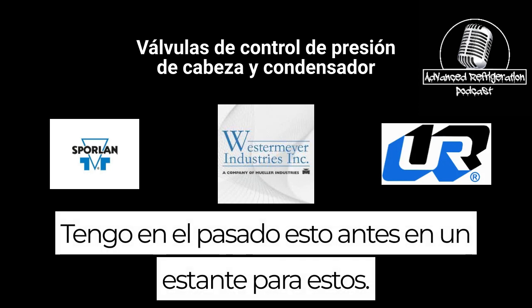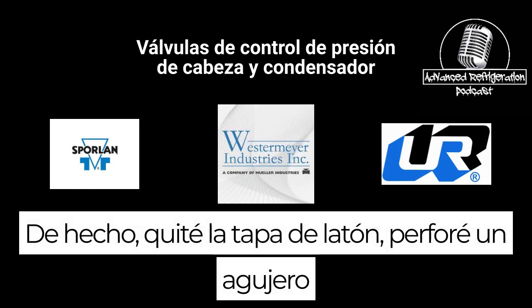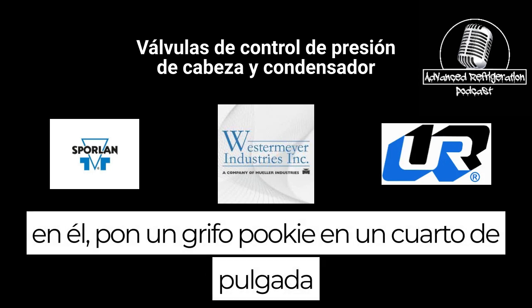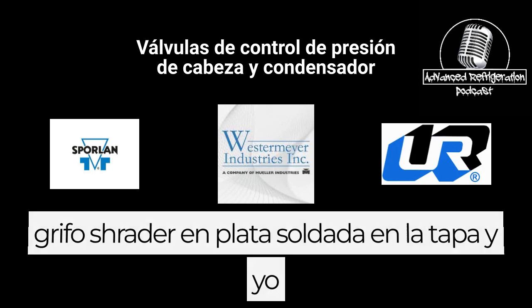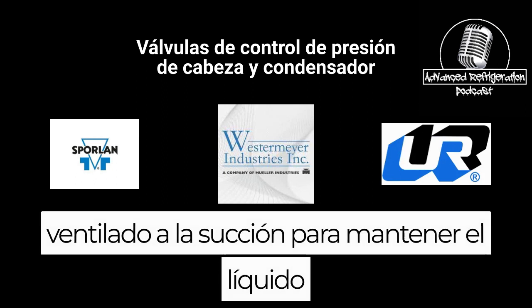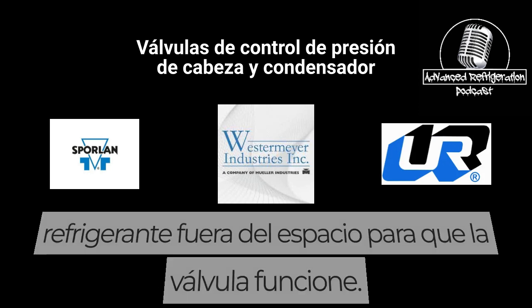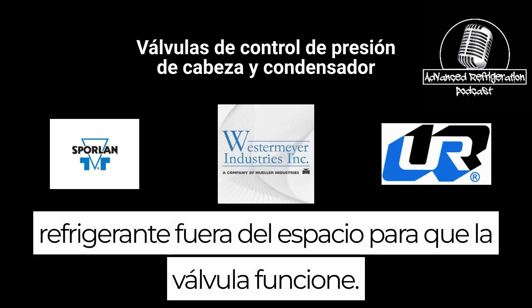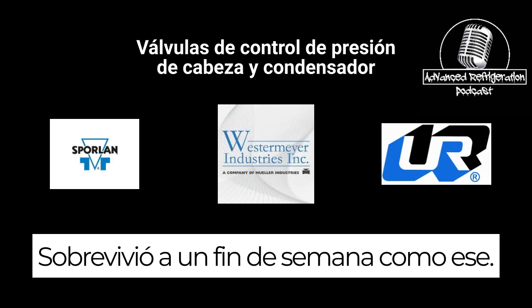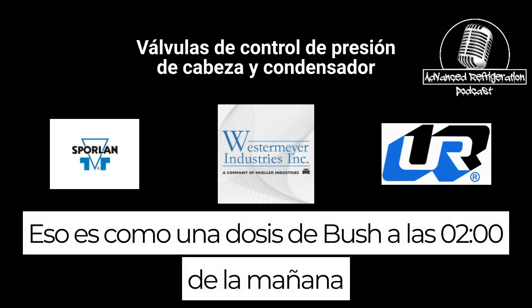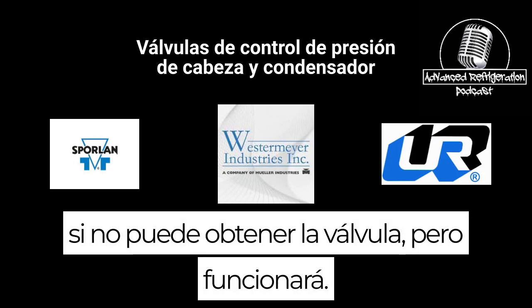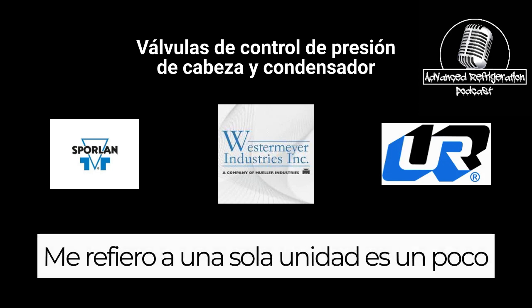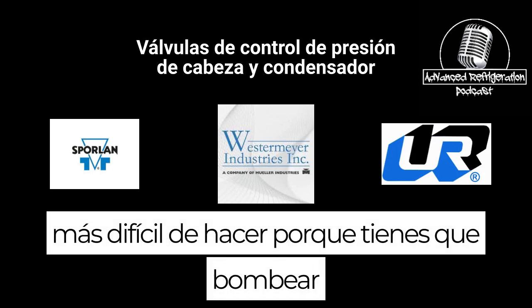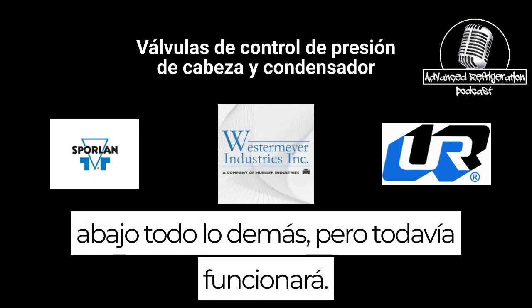I've done this before on a rack station where they had two of these. I actually took the brass cap off, drilled a hole in it, put a quarter inch strainer tap on, silver soldered on the cap, and I vented it to the suction in order to keep the liquid refrigerant out of the space so the valve would run. It made it through a weekend like that. That's a 2 o'clock in the morning fix if you can't get a valve, but it'll work. On a single unit, it's a little harder to do because you've got to pump down everything else, but it'll still work.